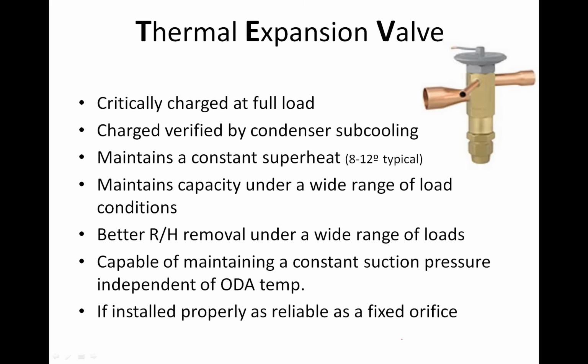So if it's set at 12, it's going to always try and maintain exactly 12 degrees, plus or minus typically 1 degree of superheat. As soon as it sees it's dropping down to 11, the valve's going to start to shut. If it's going to go up to 13, the valve's going to start to open again to try and maintain exactly 12 degrees. The difference between the opening point and the closing point of the valve is the hysteresis of the valve. That's how much it changes before the valve responds. And that can be as tight as half a degree. And when we get into electronic expansion valves, it could be as tight as 1/10 of a degree. So the valve is trying to maintain the level of refrigerant in the evaporator constant all the time.